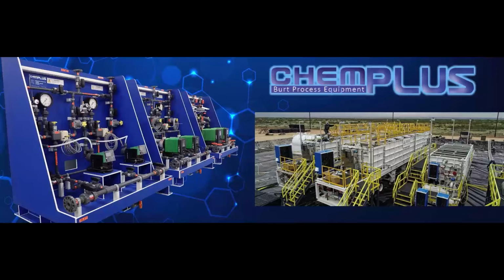Chemical feed systems are really looked at in two related but also unique ways. The first is selecting the proper pumping technology that's going to be utilized in the system. Here, in the opening slide, we have a couple of different chemical metering pump examples, but also the apparatuses that go along with them. As you can see in the same image, you have calibration, pressure gauges, back pressure, pressure relief valves, pulsation dampeners, containments, and safety enclosures. Marrying those two concepts together is really what drives making a fully functional chemical feed system.